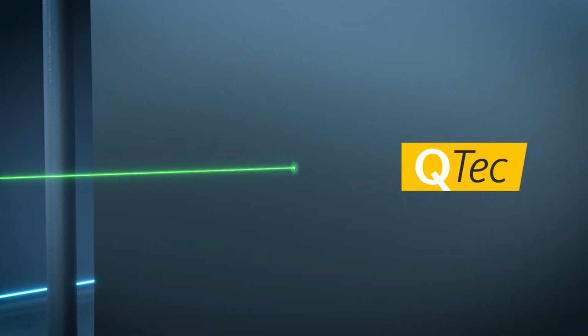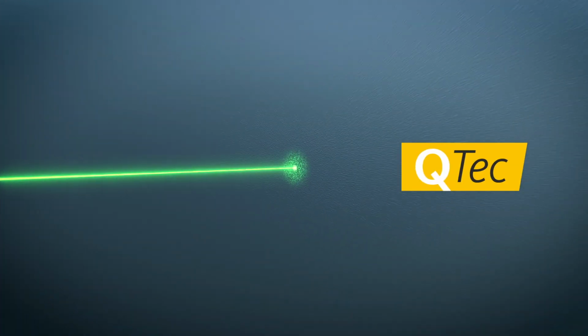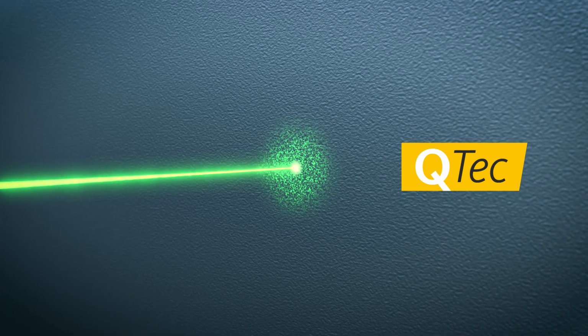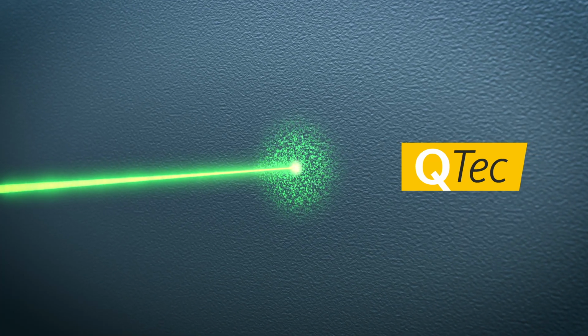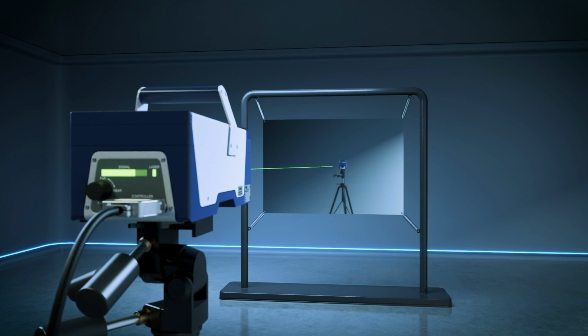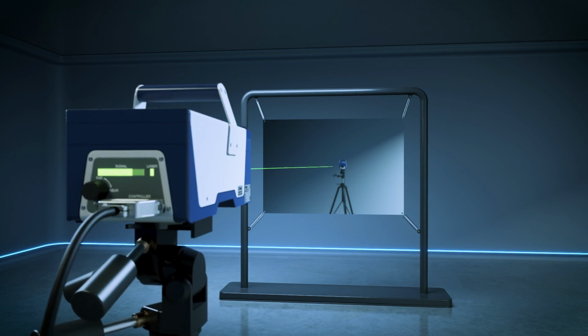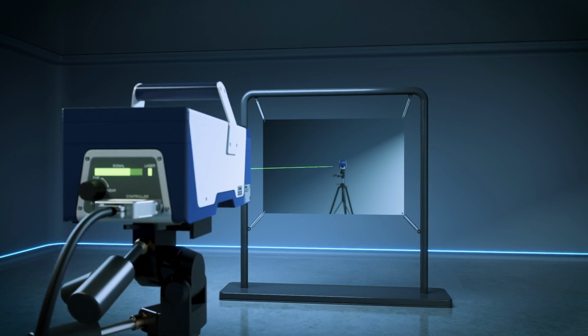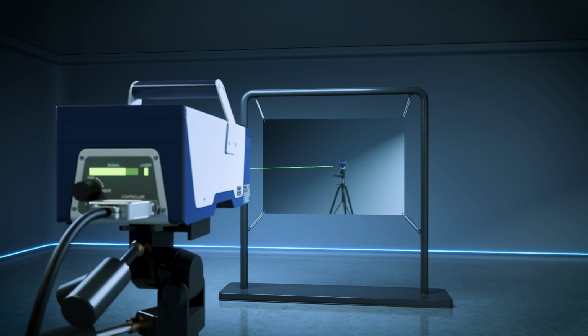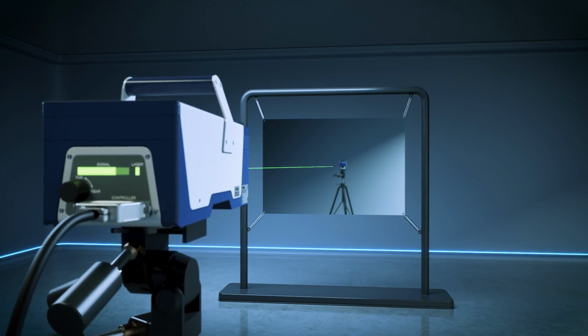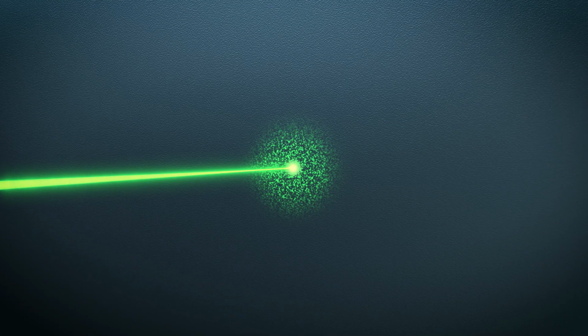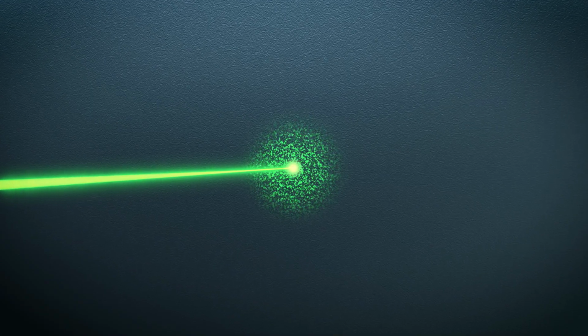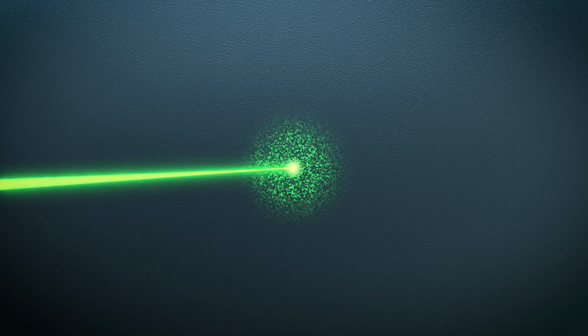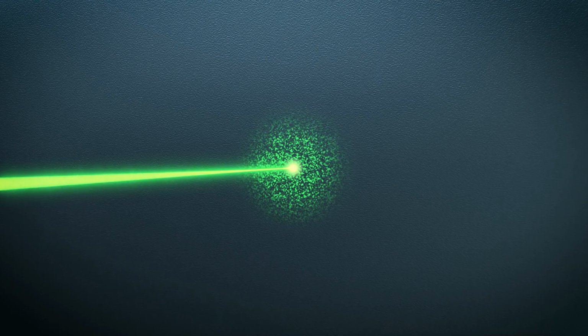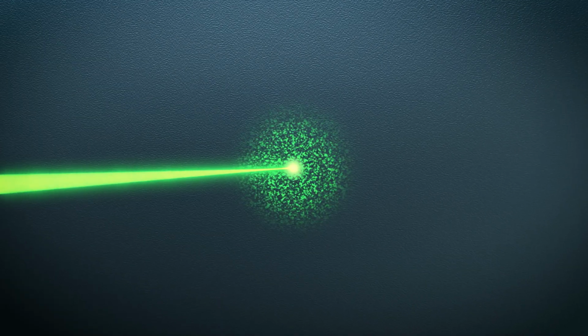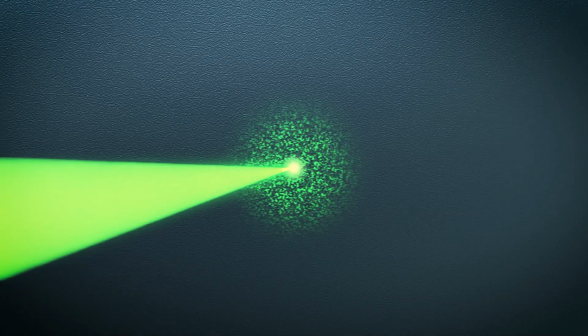With QTec, we have reinvented laser vibrometry by eliminating the root cause of noise with rough surfaces, the speckle effect. On an optically smooth surface, the reflected laser light is returned without loss to the photodetector. Vibration tests in the real world are often carried out on engineered surfaces that are optically rough. Now the light is no more reflected, but scattered. It contains dark and bright speckles. The laser point now looks grainy and the pattern changes with the perspective of the observer.